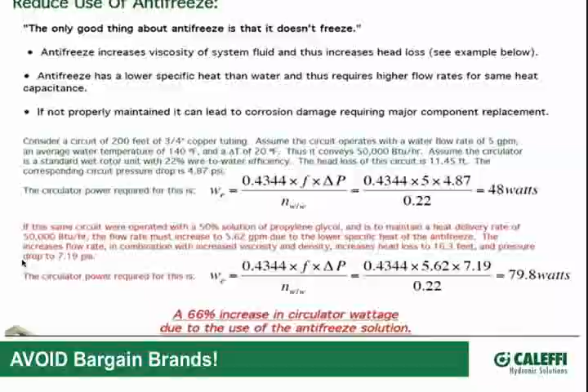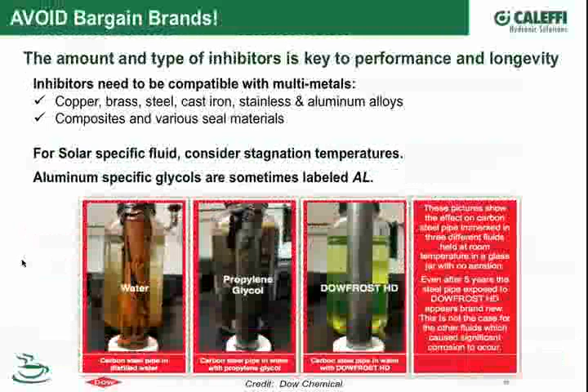It underscores the point made earlier, you're adding glycol for freeze protection. If you don't need freeze protection, you'd take an unnecessary hit in your system capacity and pumping horsepower by adding the glycol. We'll get to more slides on that as far as heat transfer too, so you take a hit on heat transfer as well as the pumpability, if that's even a word, of the fluid. That's correct.